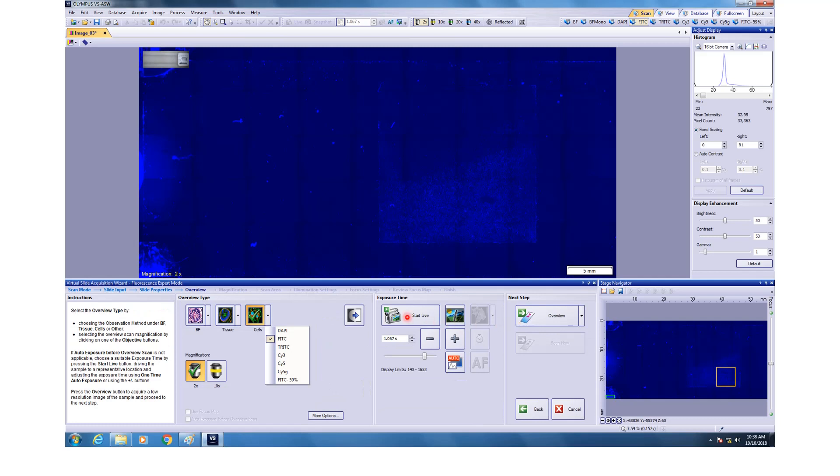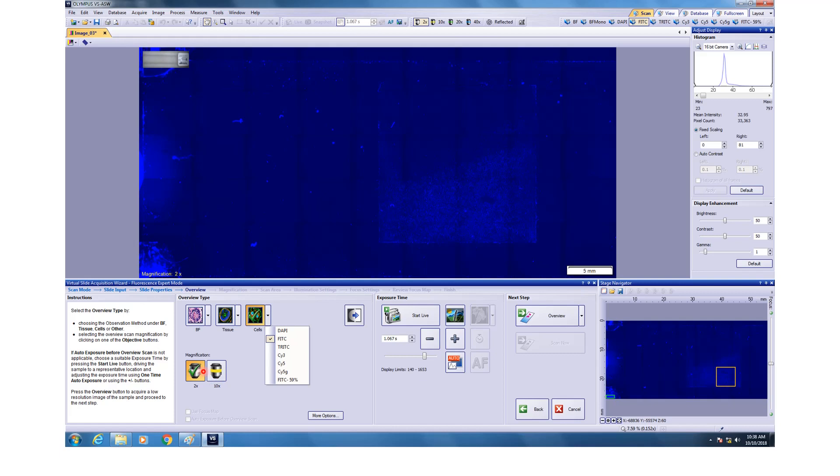After this, it will ask you what kind of overview would you like to do. If you are doing some kind of cell based imaging, then you are recommended to use this option because that will have object detection mode selective for the cells. If you are doing tissue, then you can do the tissue. If you want to do bright field, you can do bright field. There are so many options. And overview can also be done at 2x or 10x. I would recommend doing at 2x because that will save a lot of time.